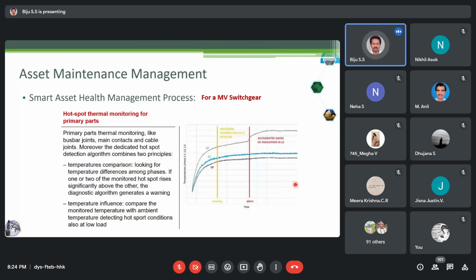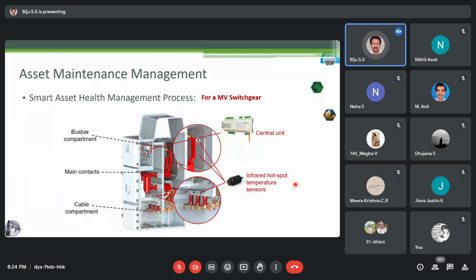There is another thing, hotspot temperature monitoring. Every breaker compartment, every breaker will have joints, and these joints are closely monitored for rising temperature. If any thermal runaway occurs, there can be a failure of the switchgear equipment. So these will be scanned, and the hotspot will be determined by checking against the ambient temperature. It also looks for temperature differences between various points, and it will generate a warning if there is any deviation from the normal. So the sensors are mounted in the MV switchgear. You have sensors in the cable compartment, main compartment, and busbar compartment, and infrared hotspot temperature sensing in the joints.